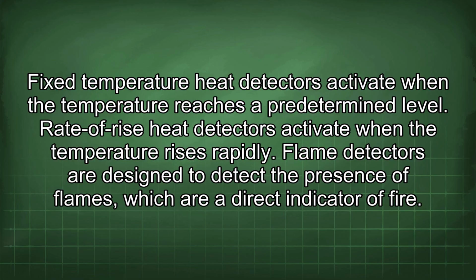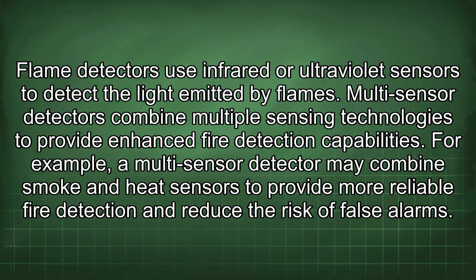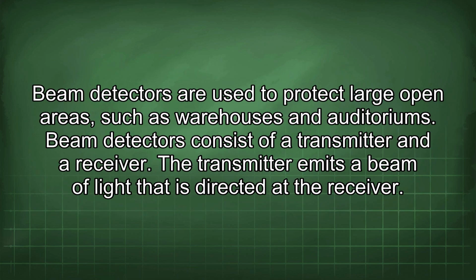Flame detectors are designed to detect the presence of flames, which are a direct indicator of fire. Flame detectors use infrared or ultraviolet sensors to detect the light emitted by flames. Multi-sensor detectors combine multiple sensing technologies to provide enhanced fire detection capabilities. For example, a multi-sensor detector may combine smoke and heat sensors to provide more reliable fire detection and reduce the risk of false alarms. Beam detectors are used to protect large open areas such as warehouses and auditoriums.